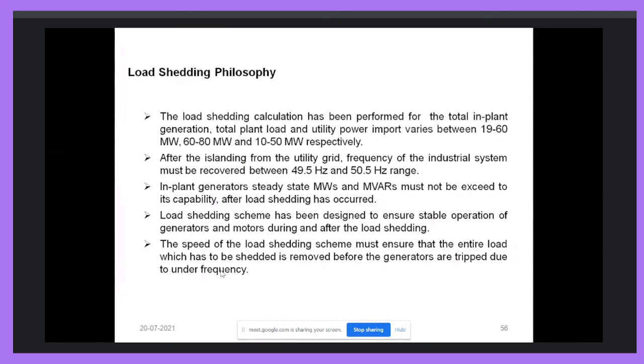Now, here we have considered different generation ranges. Okay, here the load shedding calculation has been performed for the total in-plant generation, total plant load, and utility power import, which are considered to vary: जो in-plant generation है वो 19 to 60 के बीच में vary करेगा. Okay, 19 means only one generator in operation. 60 means all the generators are in operation with the full rating. Okay, the load varies between 60 and 80 megawatt, and the power which is taken from the utility varies from 10 to 50 megawatt.